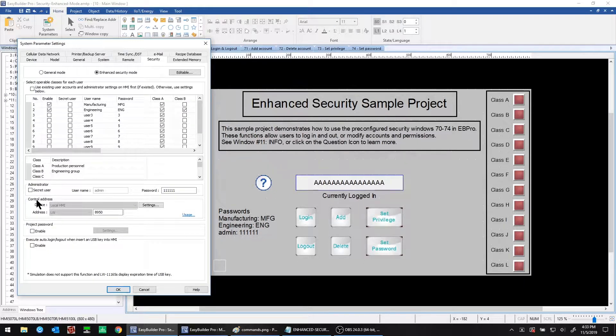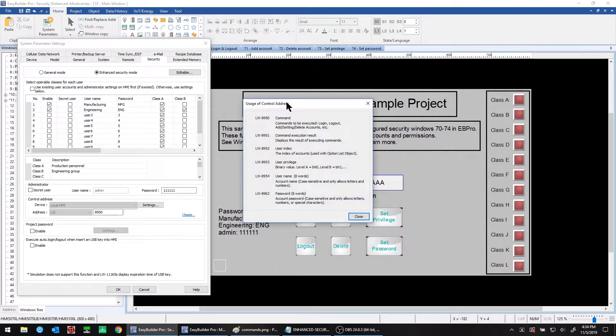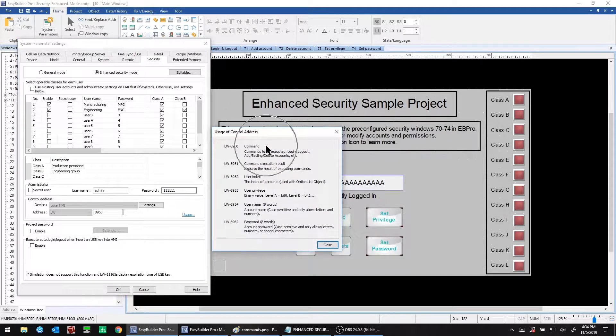Next, very important, is the control address. This is the start of a set of 20 registers used by the HMI to keep track of accounts and to modify permissions and passwords. Starting at 8950, click on usage to see some examples. First is the command or control register — you'll write values for various commands such as logging in, logging out, and adding and deleting users into this register.